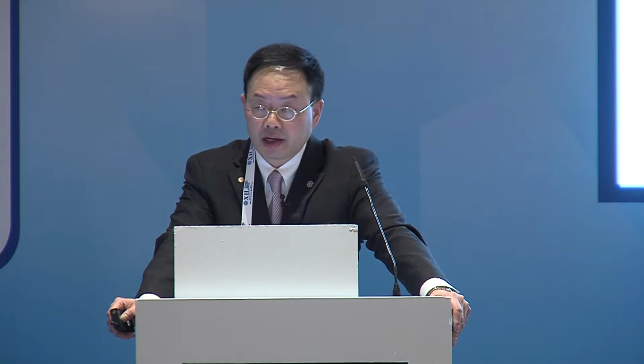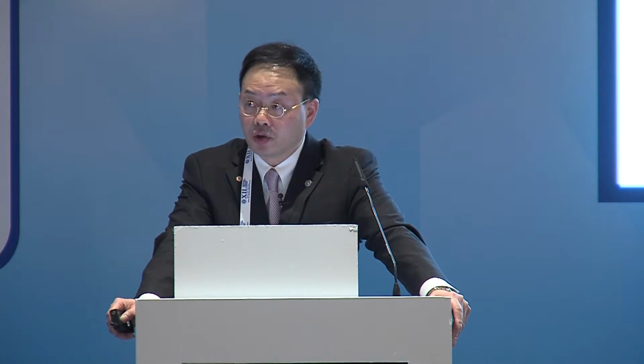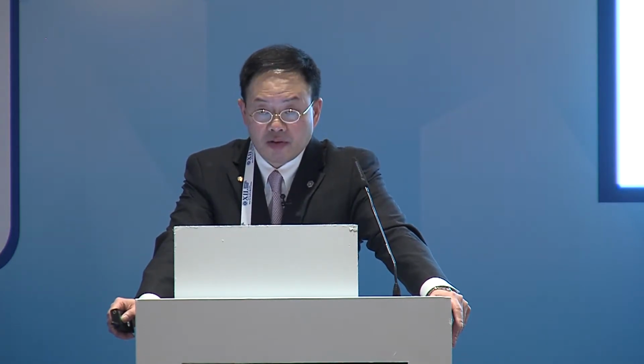Because if you locate a clean room in a very industrial, dirty, highly polluted area, and you need to bring in a certain percentage of outside air, that may impact the final cleanliness class inside the clean room. So now you have a mathematical way to estimate, but this is still at the beginning stage. IEST and ASHRAE TC 9.11 are working together to produce more documents and guidelines to support design engineers in doing a better design for clean rooms.